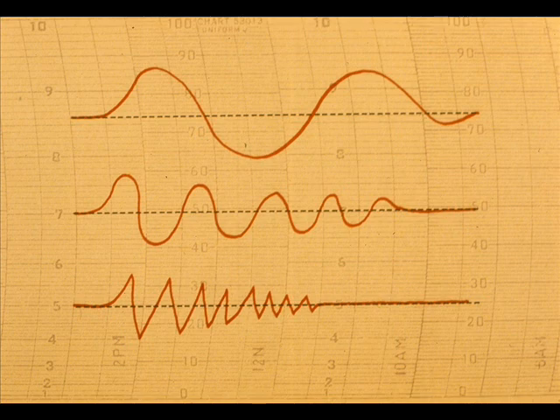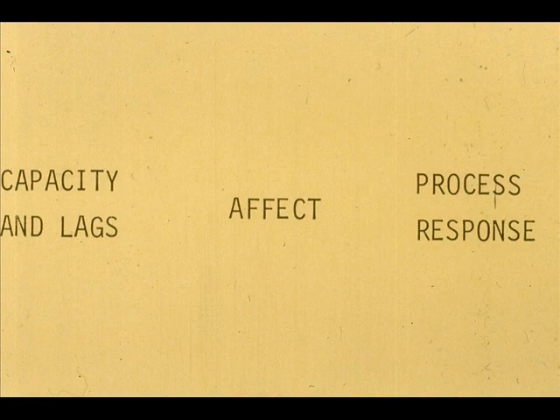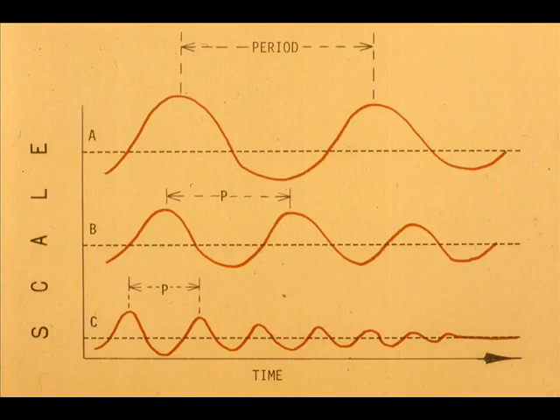All processes do not respond to an upset or a command in the same manner. The ability to respond to a given input is a function of the capacity and lags in the system. The time required for the pen to make one complete cycle on the chart is called the period of the process. The period for process C is short compared to that for process A. The period of one cycle of a process is governed by the capacity and dead time or lag in the system.